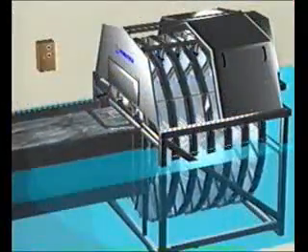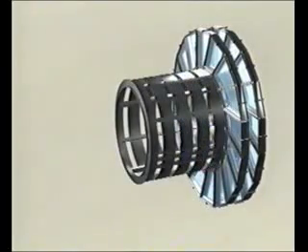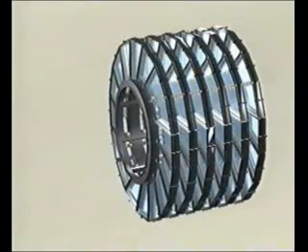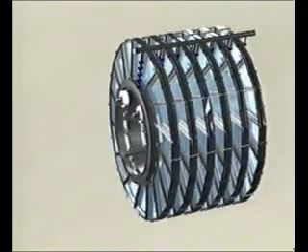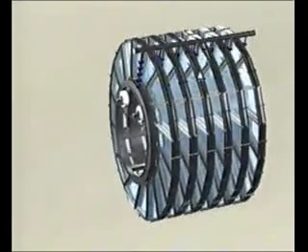The disc filter, with its more compact design and greater filtration surface, is better suited when a finer filtration is required over a large area and when the space needed for the installation is more restricted. The disc filter consists of a central drum onto which the discs with the filter media are assembled. The filter, which is suspended from a central shaft and two support wheels, rotates when the filter cloth is backwashed.